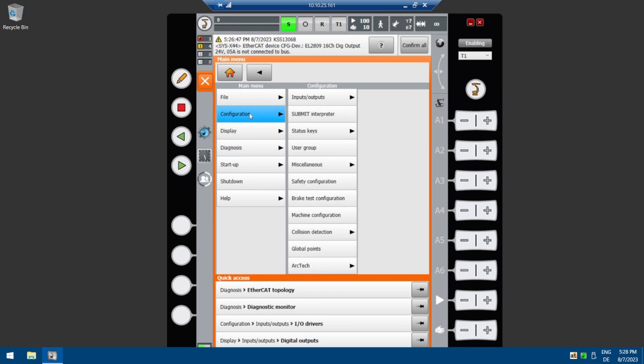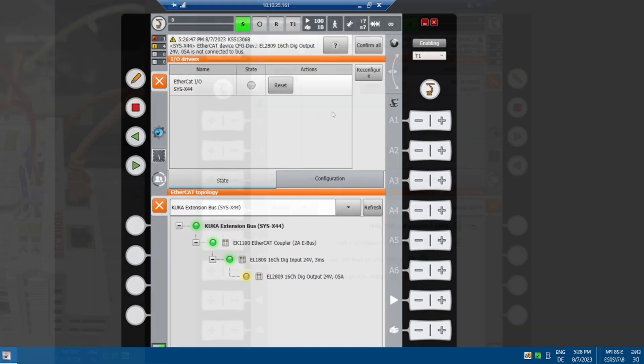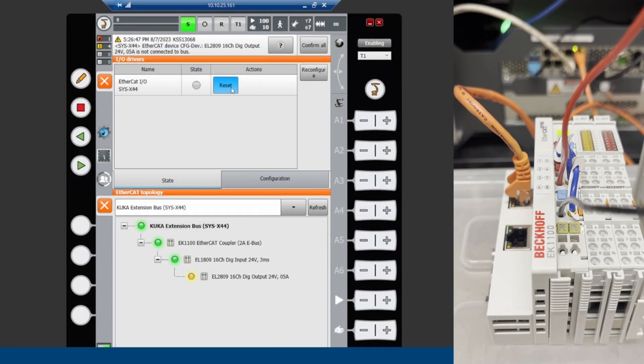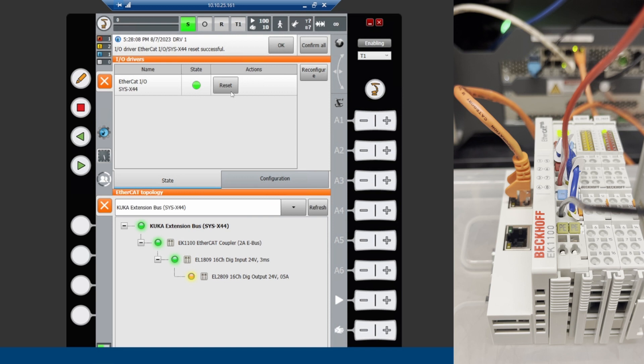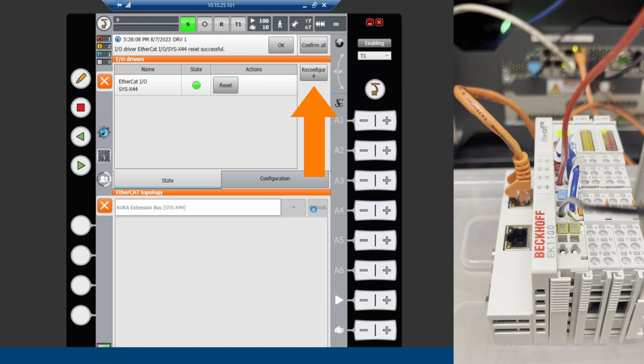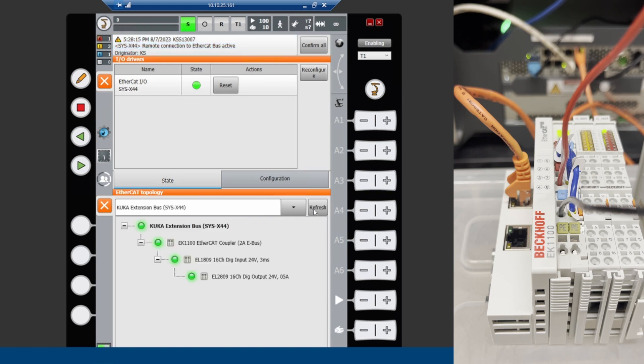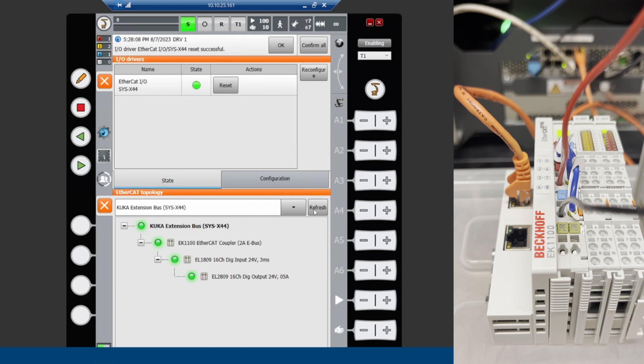We must refresh the status of the bus. On the SmartPad, select Menu, Configuration, Input Output, then I/O Drivers. Refresh the bus by clicking the Reset button. If this doesn't work, you can select Reconfigure. After the bus is refreshed, the output LED will turn back on and the status of the EL2809 will turn green.